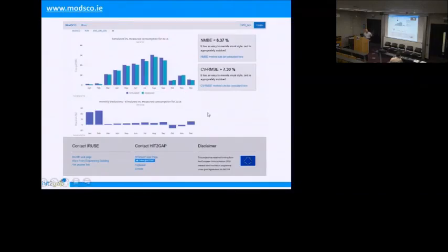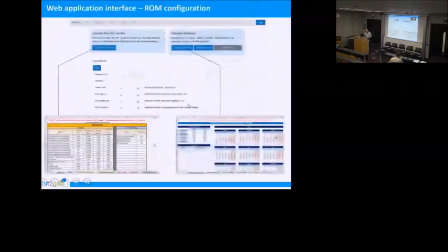So once we know that this model is calibrated, we can start changing and see what's the impact on energy consumption. In order to do that, this is just going back to the inputs of the model. So this is what I was telling you about the Excel file. There is a selector for materials, for construction, for arrangements, and then the Excel file calculates the resistance and capacitance of the building. Okay. And then for the schedule, there is a schedule generator. So you have a schedule for occupancy, for loads, and for seasonality. And then it generates the input for the model for you. Okay.